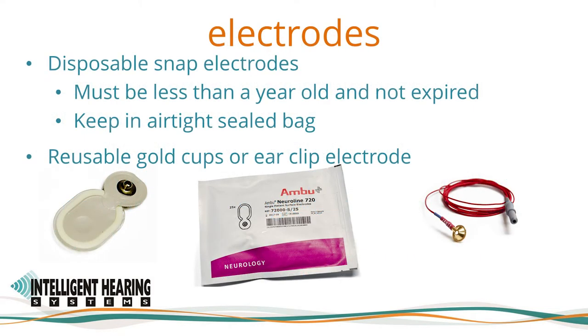The practice guidelines of the American Academy of Audiology state that disposable electrodes are recommended for infection control. IHS has validated the equipment with the Ambu Neuroline disposable electrodes and recommends these electrodes. Please be sure that your disposable snap electrodes are kept in an airtight sealed bag, that they are less than a year old and not expired. The electrodes are pre-gelled and should not be dry before you start using them. Fresh electrodes will have gel on the center sponge. Reusable gold cup electrodes as well as clip electrodes can also be used — please be sure these are clean and not tarnished.